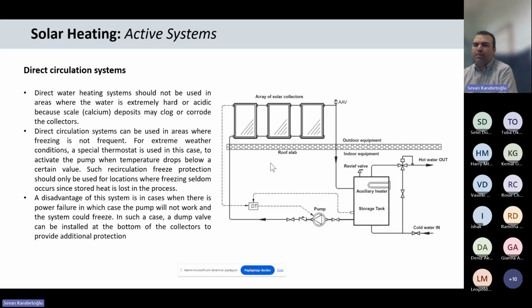Again, another important part is freezing. These direct circulation systems can be applied only if freezing is not frequent, so the weather conditions should not be harsh. Therefore, we have to prevent these harsh conditions if you want to implement direct circulation systems. And one disadvantage of the system is a power failure, in which case the pump will not work. The heart of the system is the pump. If the pump does not work, then there will be no circulation, so heat transfer should not occur in these cases. So there will be some additional protection for, let's say, the electrical pumping.